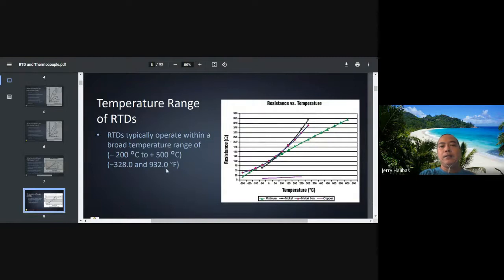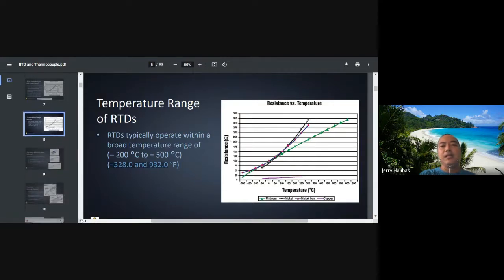So an RTD has a range of negative 200 degrees Celsius to 500, particularly the platinum type. That's the platinum's range. In Fahrenheit, that's negative 328 to 932. But then again, the thermocouple has a broader range compared to the RTD.